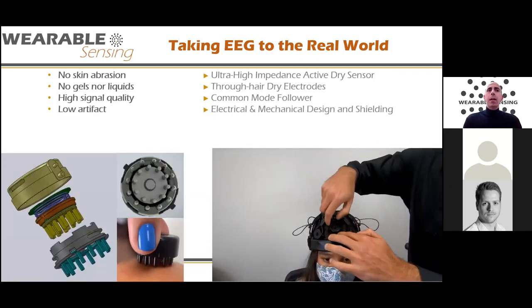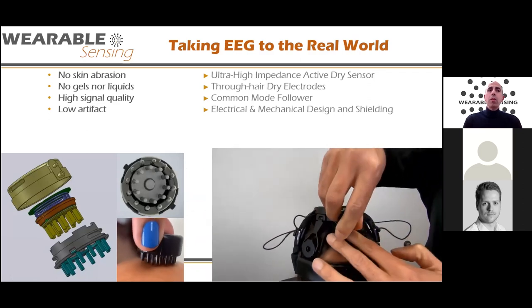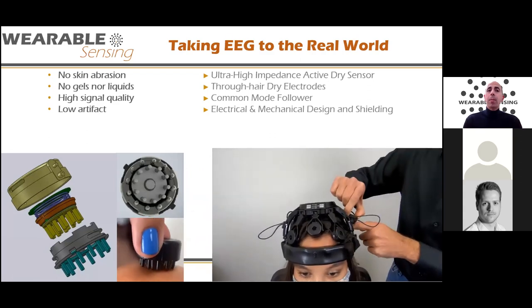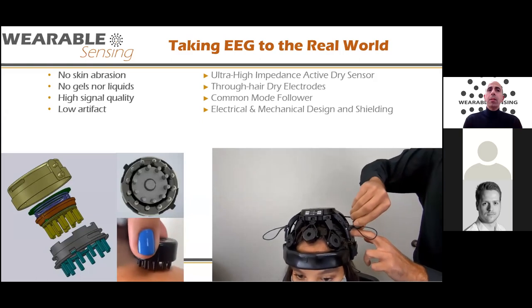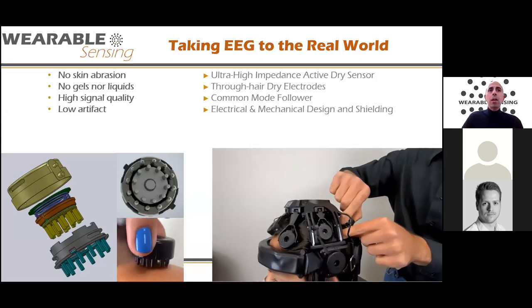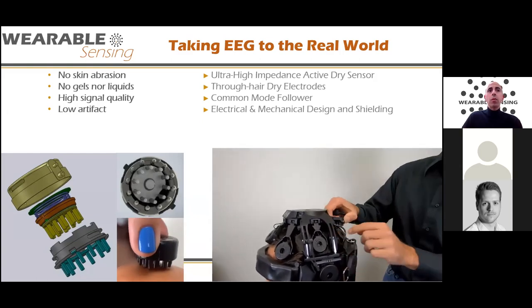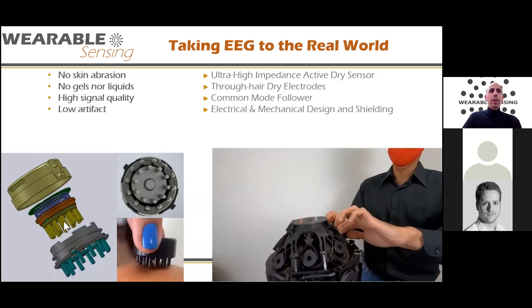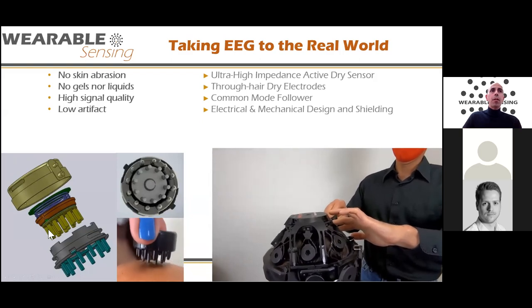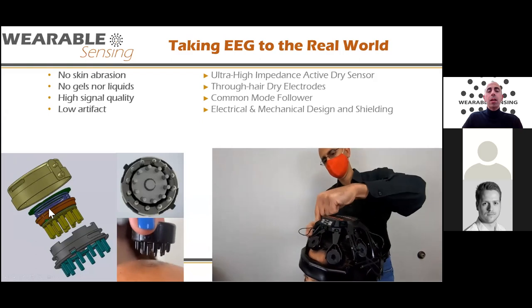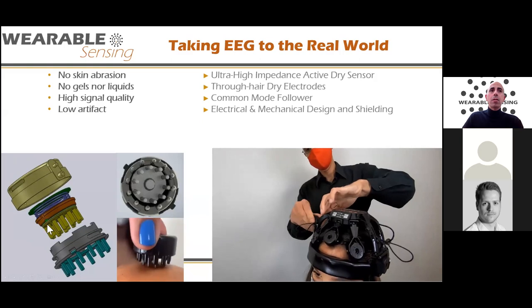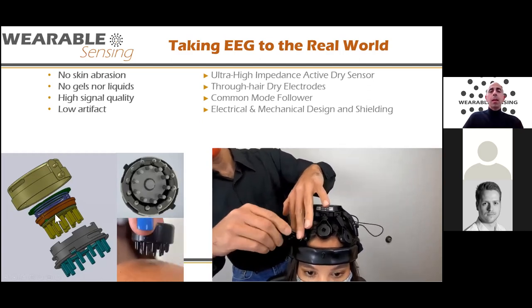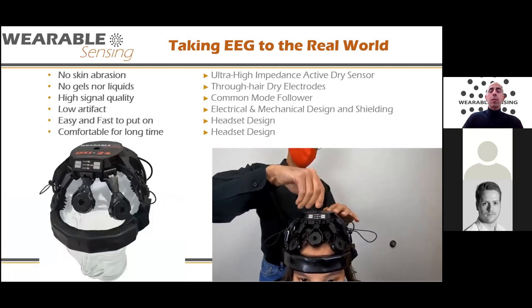Sponsors asked how we deal with artifacts given high contact impedance from dry electrodes. We did electrical and mechanical designs — springs behind the electrode keep the sensor in place when the headset moves. We placed the amplifier immediately behind the electrodes and encased everything inside a Faraday cage, which shields from electromagnetic interference. Now the only signal source is inside the head, amplified before leaving the headset.